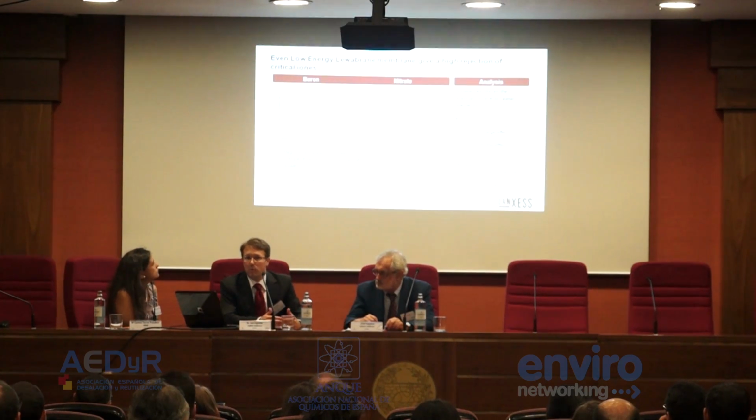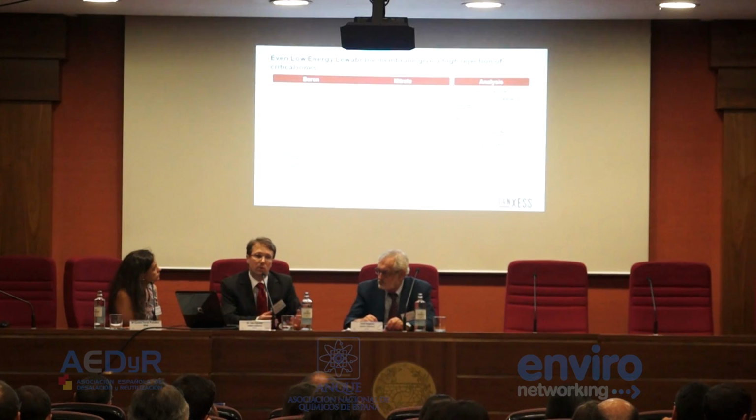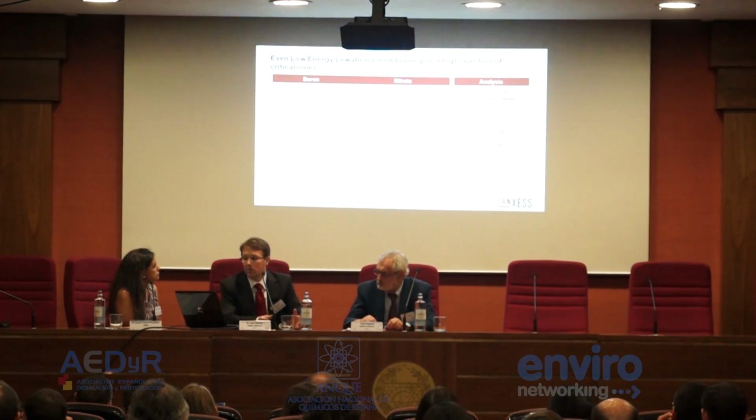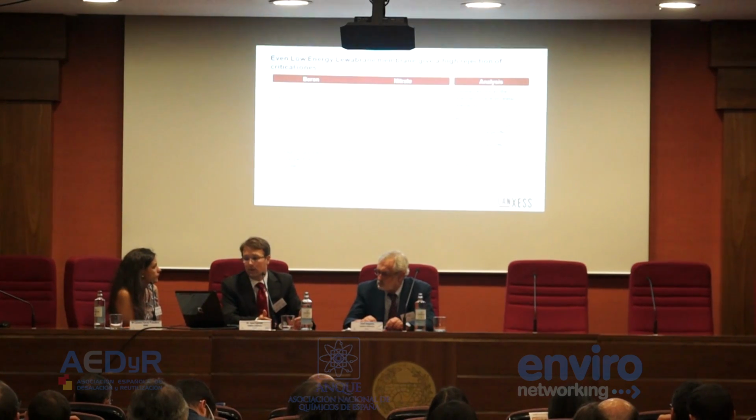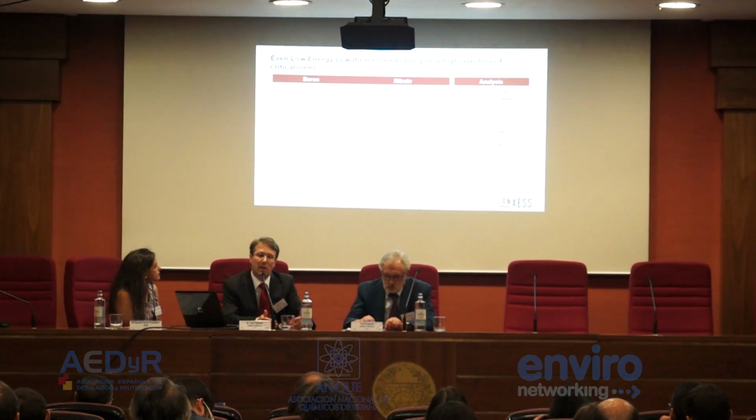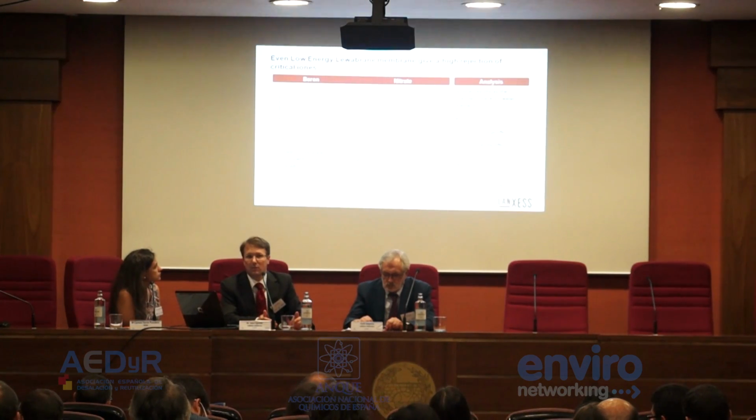Well, more and more common in the market are the low energy types of membrane, especially if you just want to treat some river water. There we tested it also, and here it was supported that we have also a higher rejection of boron and nitrate. And we made a comparison with the different design softwares, and we found out that we have a little bit higher pressure compared to the market leader, but we had a 25% higher rejection for it.